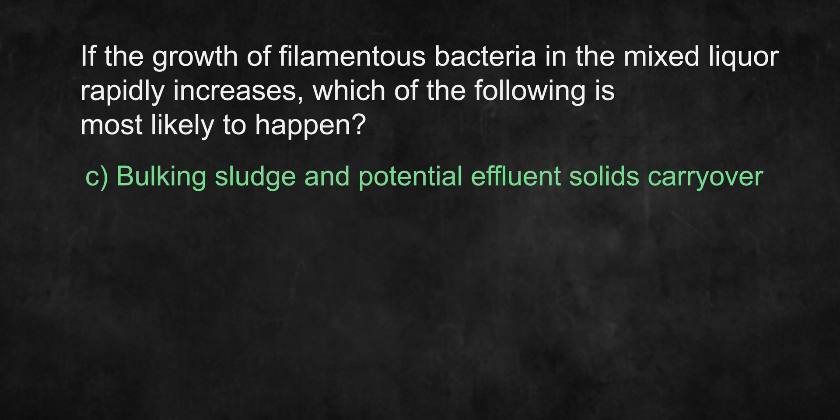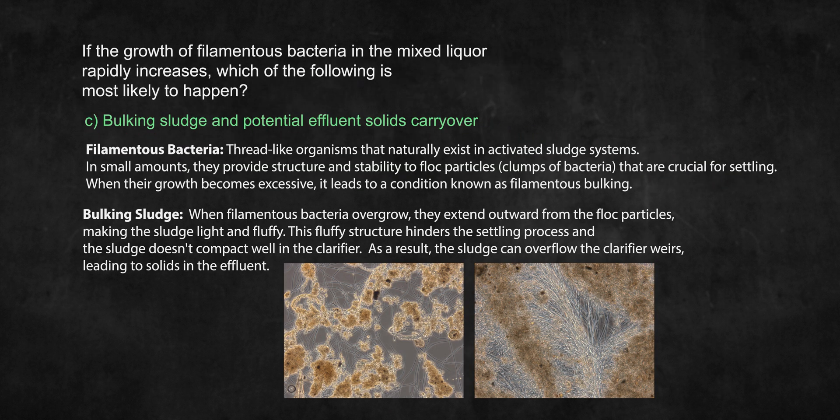The answer is C: bulking sludge and potential effluent solids carryover. Filamentous bacteria are thread-like organisms that play an important role in activated sludge systems. They're necessary in small amounts because they provide structure and stability to floc particles. However, excessive and uncontrolled growth of filamentous bacteria will lead to a condition known as filamentous bulking, also commonly referred to as bulking sludge. Bulking sludge under a microscope may look similar to the pictures on the screen.